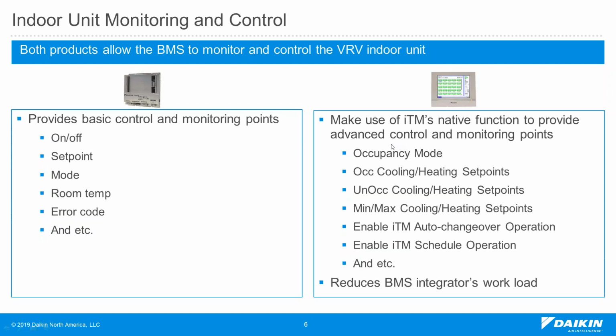For example, instead of providing just an indoor unit on/off point, it provides the integrator occupancy mode point, and the BMS can set occupied, unoccupied, and standby. And instead of providing just one single set point, it provides occupied cooling set point, occupied heating set point, unoccupied cooling and heating set points. So in this way, the BMS can make use of ITM's native logic to adjust the set point based on the different occupancy mode.